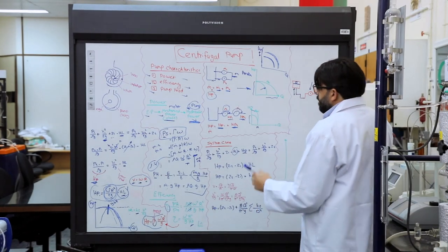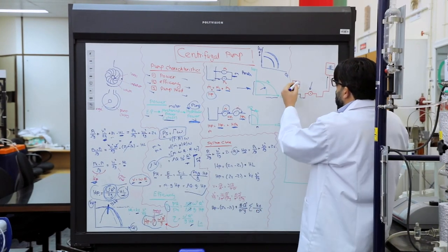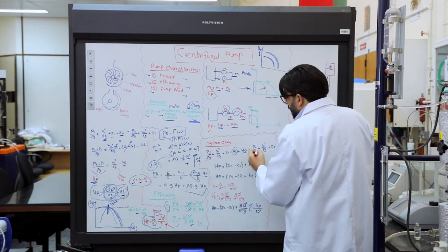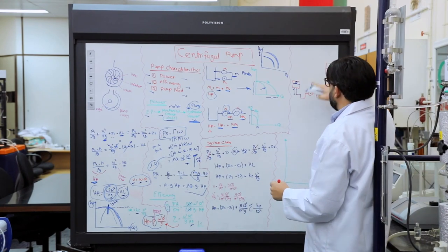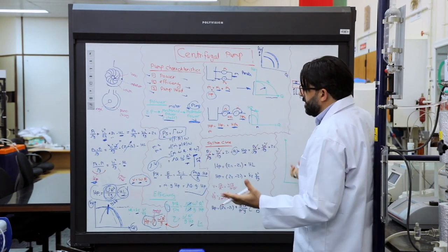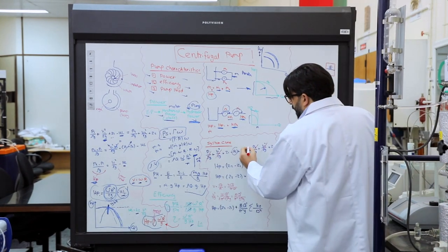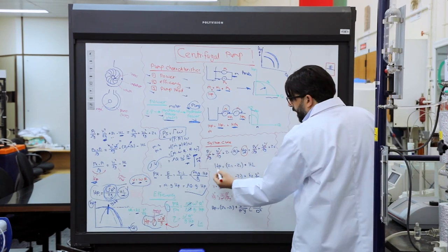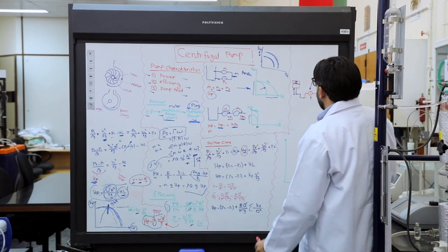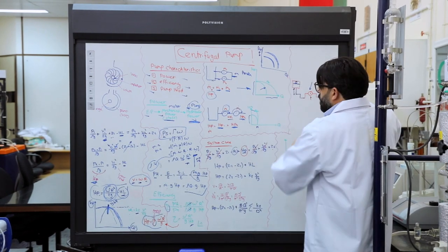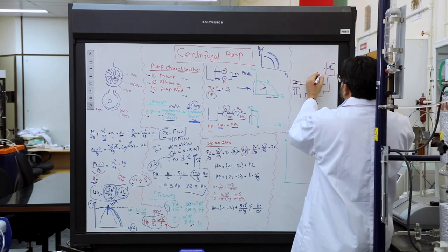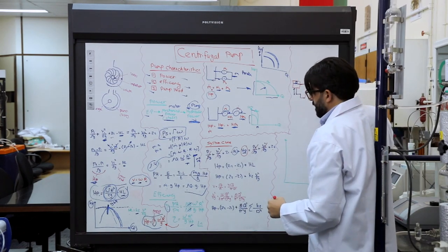So now, between point 1 and point 2, atmospheric pressure and atmospheric pressure are the same, so we can cancel P1 and P2. If the source is a storage tank, it is static, so the kinetic energy is zero. Or if it is moving but the same, it will also cancel. So now the pump head in the system should equal Z2 minus Z1 plus HL, the head loss. That means the required pump to be installed in this system should cover the difference in height, Z2 minus Z1, plus all losses in the system.